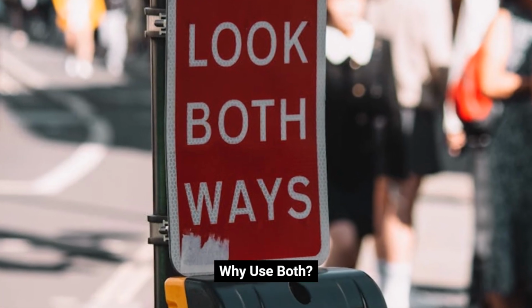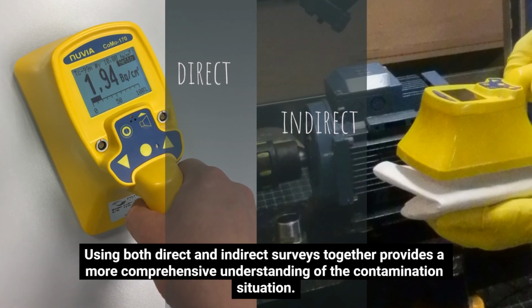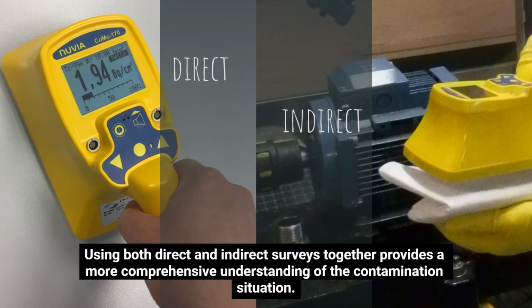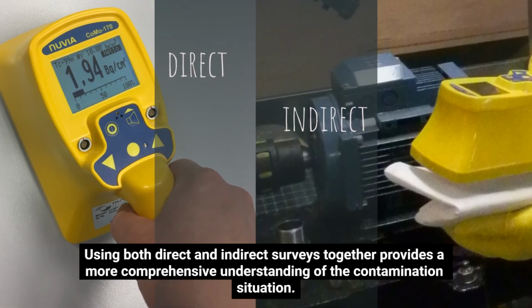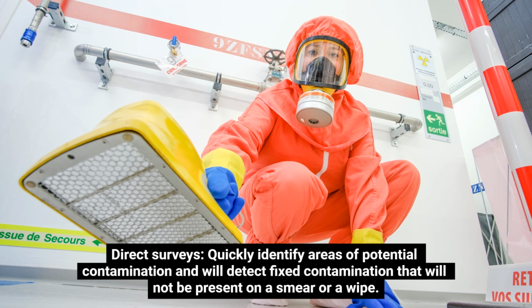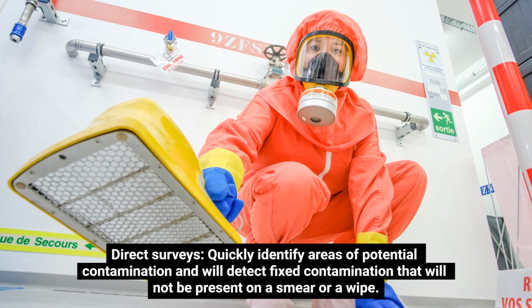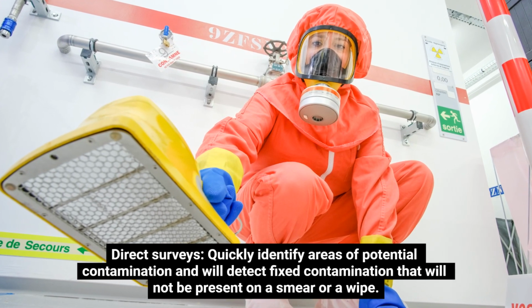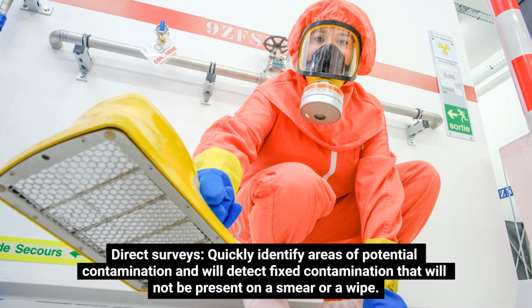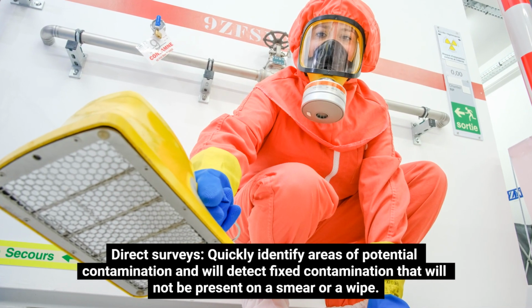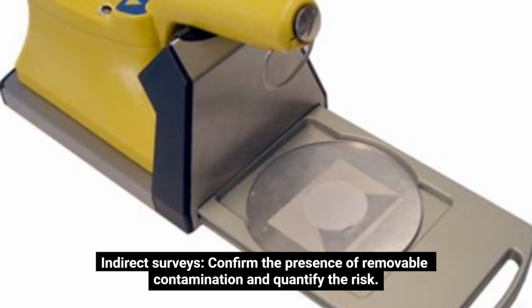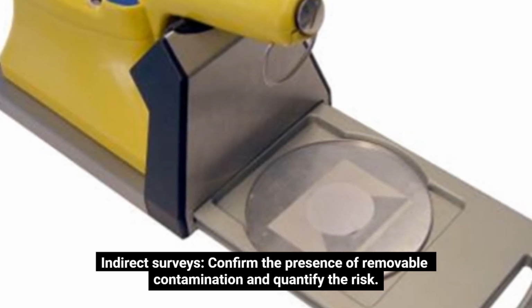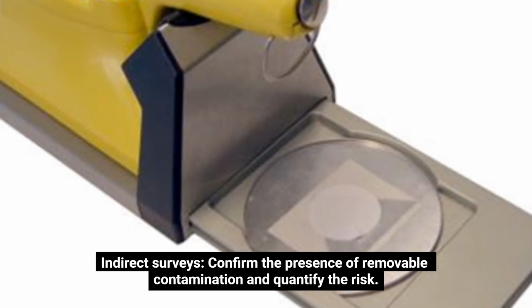Why use both? Using both direct and indirect surveys together provides a more comprehensive understanding of the contamination situation. Direct surveys quickly identify areas of potential contamination and will detect fixed contamination that will not be present on a smear or a wipe. Indirect surveys confirm the presence of removable contamination and quantify the risk.